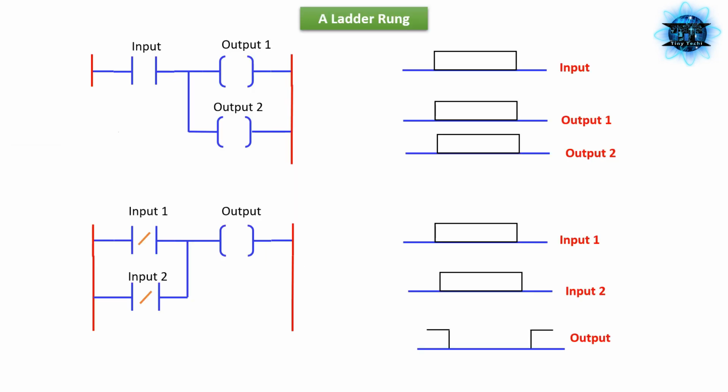Switches, contacts, and other devices are inserted in the ladder line starting on the left power rail. All coils, pilot lights, and other outputs are on the right power rail. An input line can feed more than one output. If it does, the outputs are connected in parallel. Switches, contacts, and other devices may be multiple contacts in series, parallel, or series parallel.